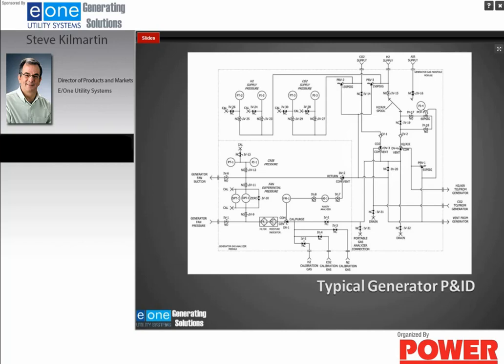It will go through a filter and a moisture indicator. There's a three-way valve that will direct it towards the analyzer. It goes through a flow meter, through the analyzer, another three-way valve, and then back to the generator fan suction. So this particular analyzer is connected across the generator fan. It is relying on the generator fan pressure to create a flow through the analyzer.